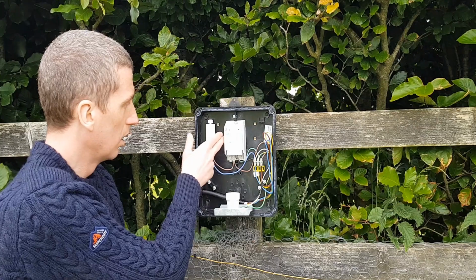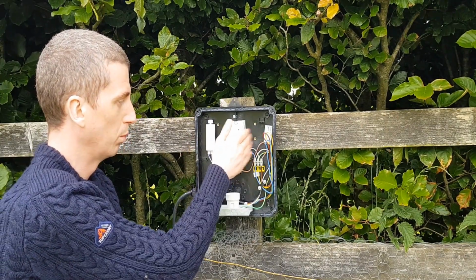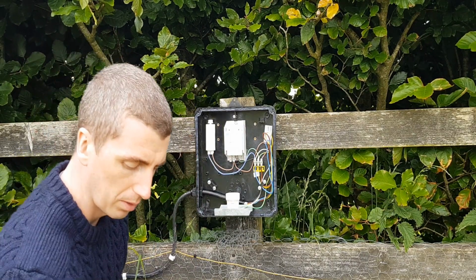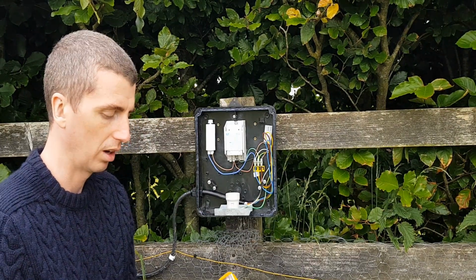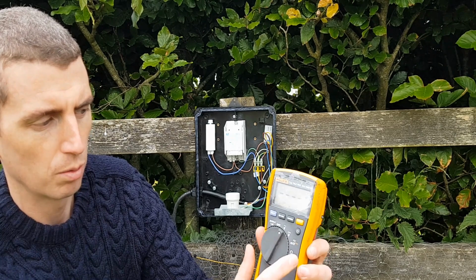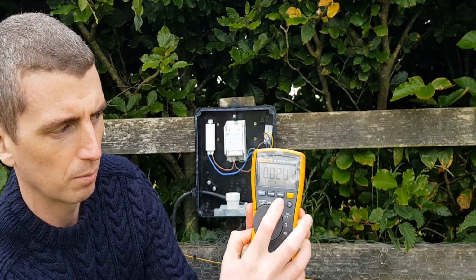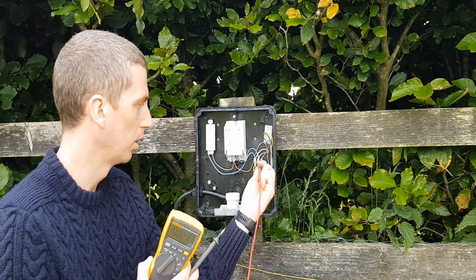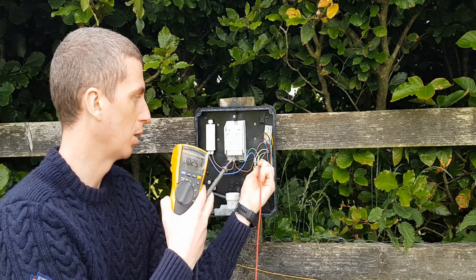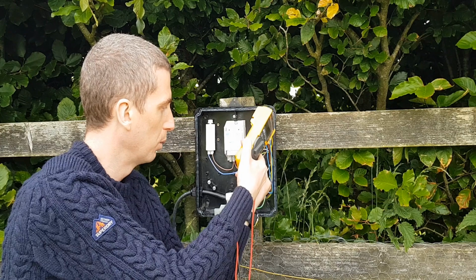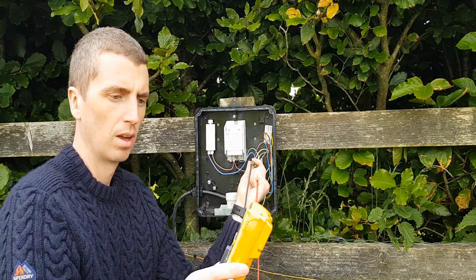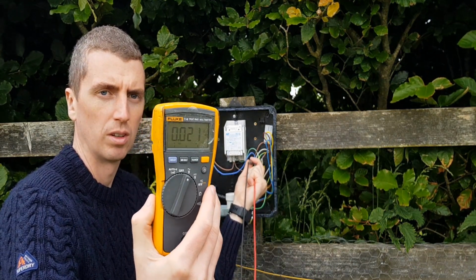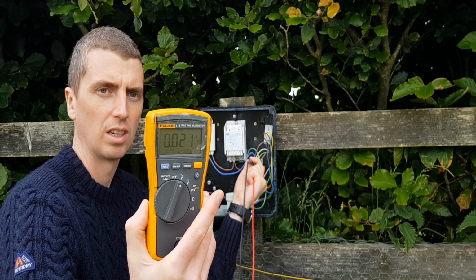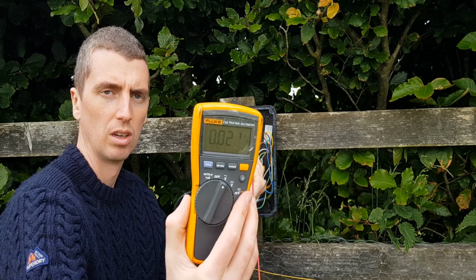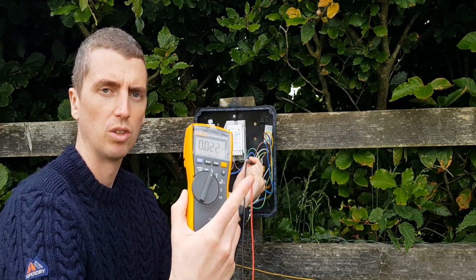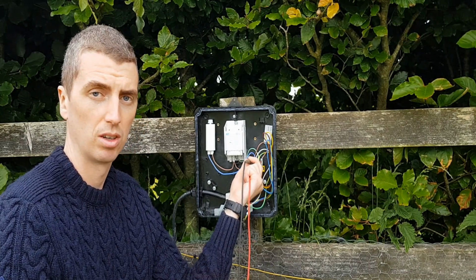So what I'm going to do now, I'm going to remove this igniter capacitor and I'm going to remove this ballast. Before I do any of that, I need to make sure that there's no electrical supply on the light, and to do that I'm going to move my multimeter to this setting here. I'm going to put the red probe in where the brown cable terminal is. I'm going to put the black probe where the blue cable is. If you get a reading of 230 volts, there's still electrical supply on this floodlight, and you need to disconnect the electrical supply before proceeding. But as you can see, the voltage from the multimeter is 0, so there is no electrical supply on this particular floodlight, so it's safe to work on.